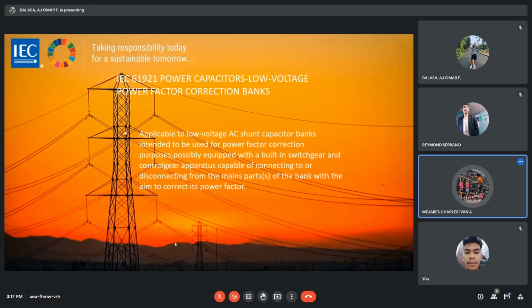Next is IEC 61921, power capacitors, low voltage power factor correction banks. Applicable to low voltage AC shunt capacitor banks intended to be used for power factor correction purposes, possibly equipped with a built-in switchgear and control gear apparatus capable of connecting to or disconnecting from the mains parts of the bank with the aim to correct its power factor.